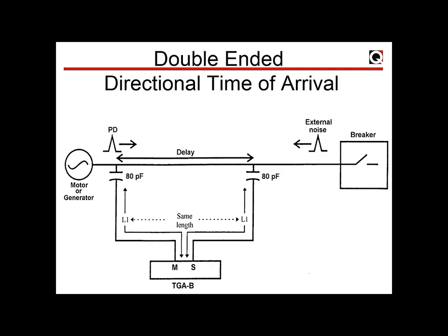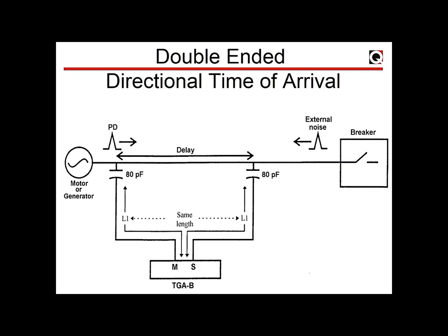In the IRIS approach, two sensors are recommended per phase. For turbo generators or large motors connected to bus conductors, two sensors are installed on the bus — one machine-side and one system-side. These compare pulse arrival time so the operator easily sees what is happening in the machine versus the system. The most critical aspect of any PD measurement is rejection of external noise, and the two-sensor method achieves this by comparing arrival times of pulses from the system and from the machine, separating them into two columns automatically.